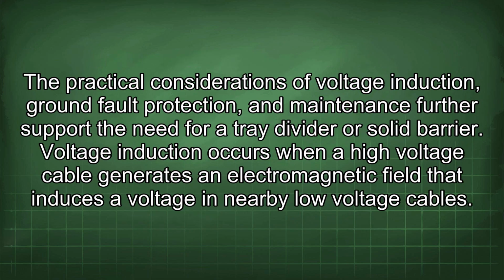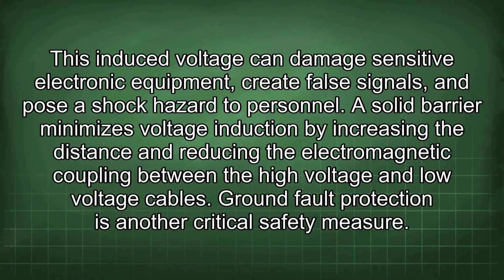The practical considerations of voltage induction, ground fault protection, and maintenance further support the need for a tray divider or solid barrier. Voltage induction occurs when a high voltage cable generates an electromagnetic field that induces a voltage in nearby low voltage cables. This induced voltage can damage sensitive electronic equipment, create false signals, and pose a shock hazard to personnel. A solid barrier minimizes voltage induction by increasing the distance and reducing the electromagnetic coupling between the high voltage and low voltage cables. Ground fault protection is another critical safety measure.